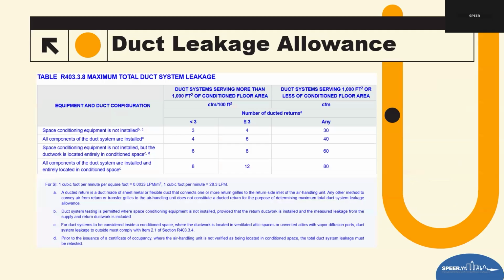This is the new table for duct leakage. One of the biggest changes is adding this. Instead of saying a 4 CFM per 100 square feet rule, it says this is all based on certain criteria. Starting with the purpose of the table, this table sets the maximum duct leakage for TDL, total duct leakage, based on the equipment configuration, whether it's installed or not, and how the system is installed, at time of testing.